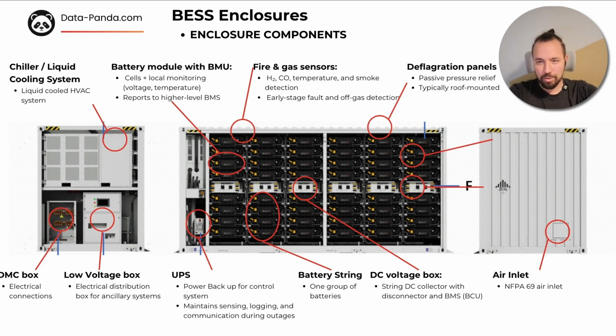And finally, we have the DMC box. That's designed for external DC connections. So that's the box where we'll have this container connected to our PCS. Inside the DMC box or near it, there could be a fire control panel where all the gas sensors will be connected. So it will do coordination, and usually it's placed near the DMC box or in the low voltage box.